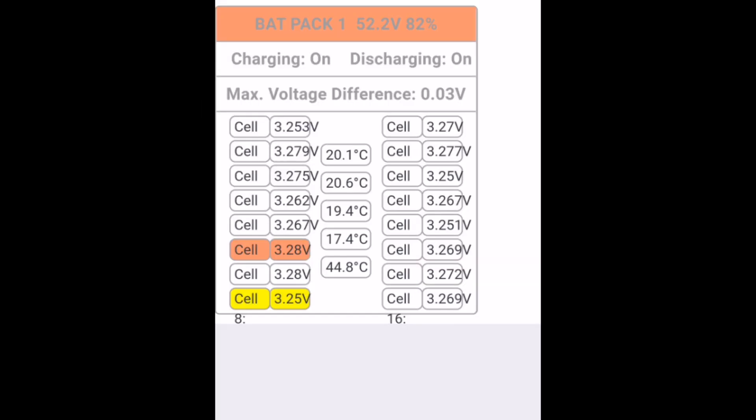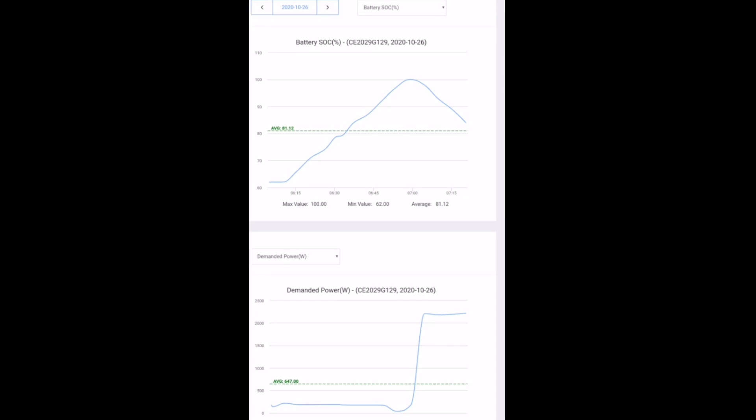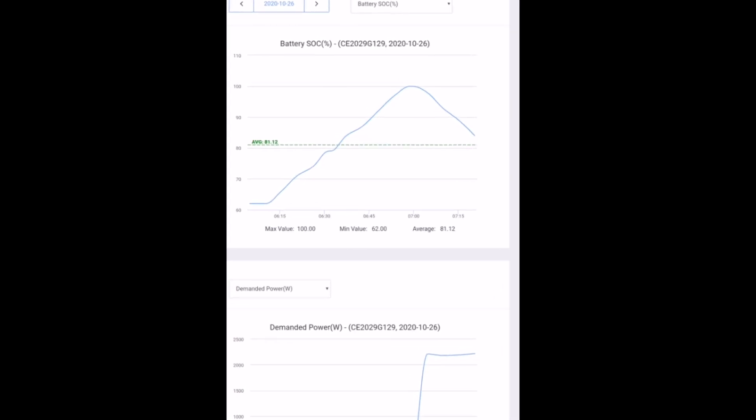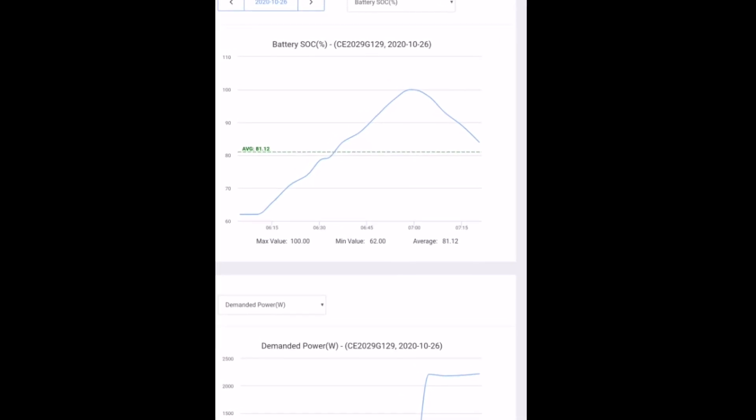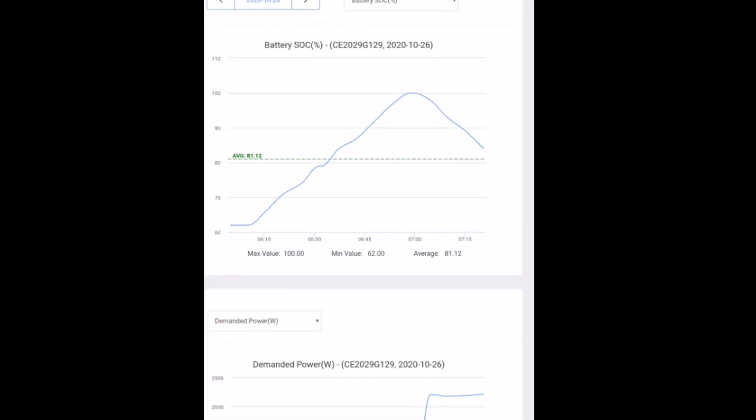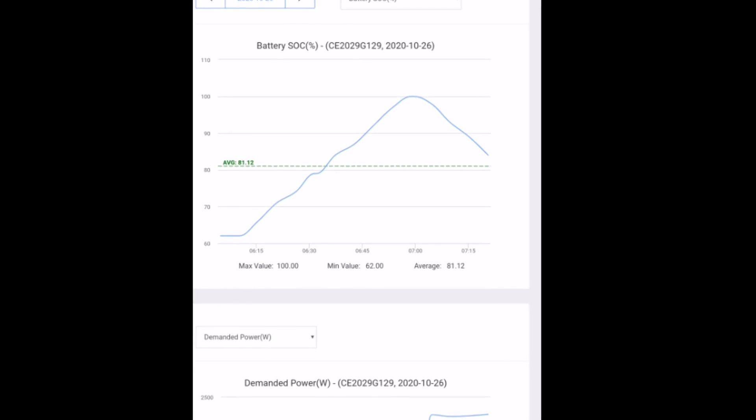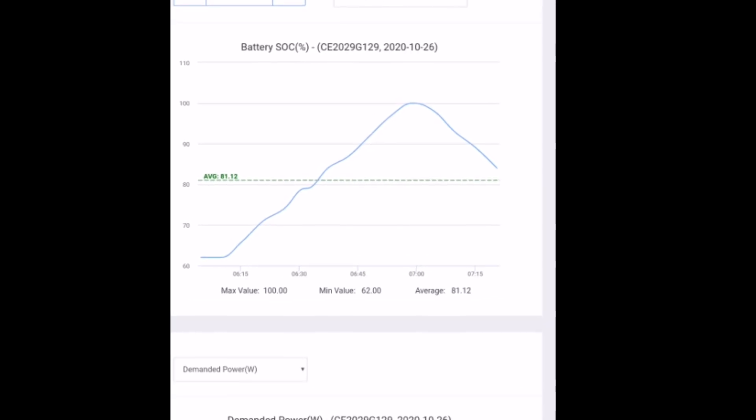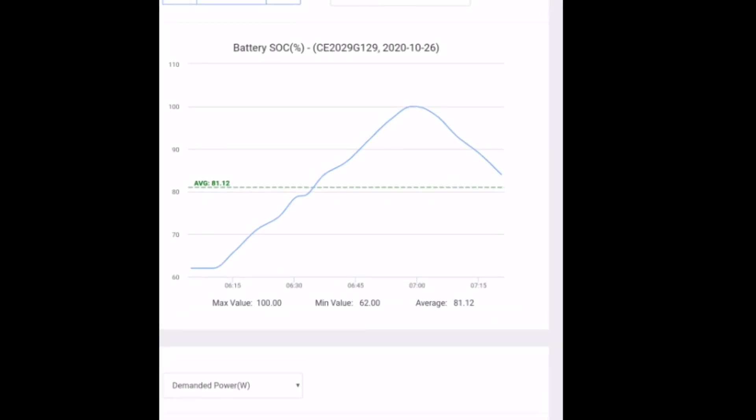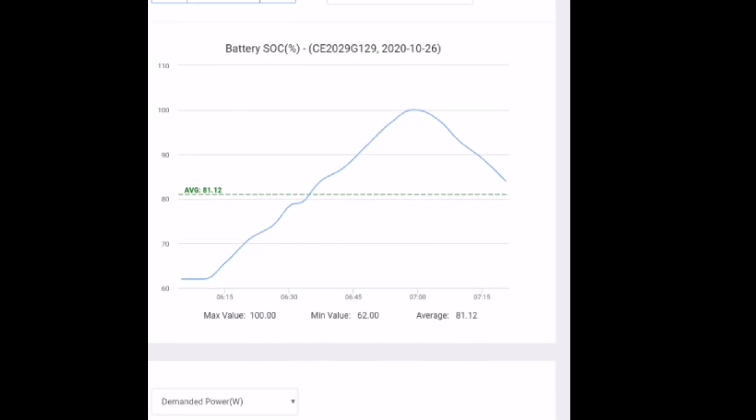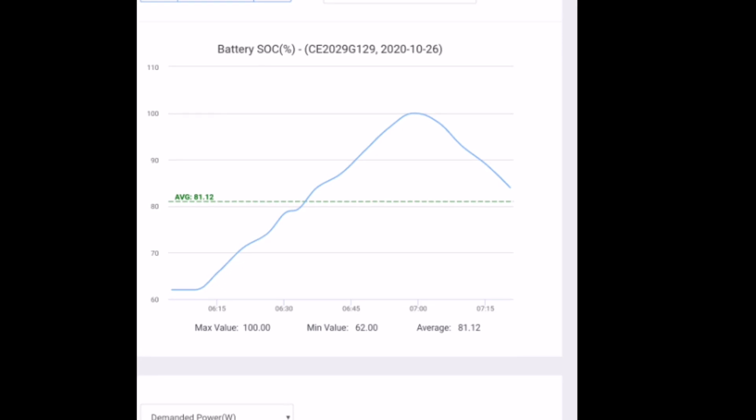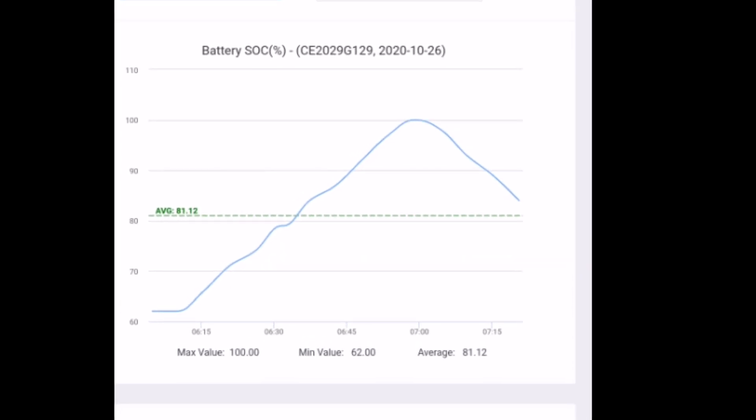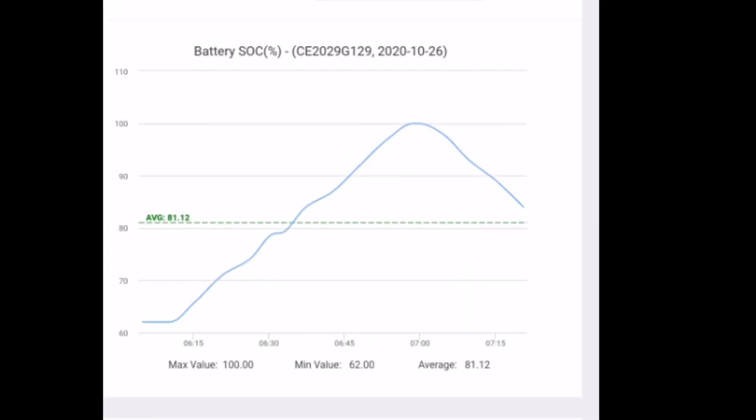20 minutes into the test, the battery temperature has risen up to between 17 and 20 degrees. Quick look at the state of charge graph. And we can see we reached 100%, stayed there for a short time. And now we're on the way down discharging. And also the AC demanded power, that's nice and consistent around 2.2, 2.3 kilowatts.